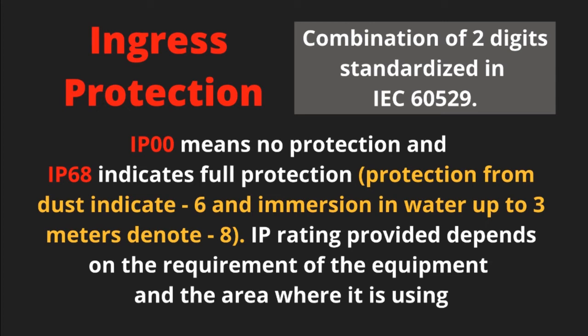IP 00 means no protection. IP 68 indicates full protection: 6 indicates protection from dust and 8 denotes immersion in water up to 3 meters. The IP rating provided depends on the requirement of the equipment and its area of use.